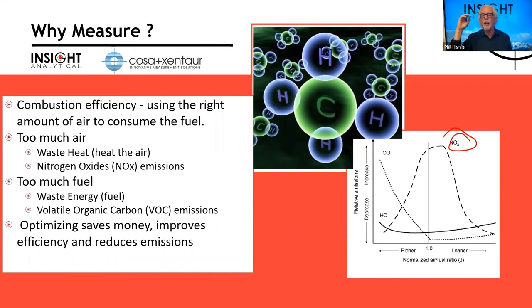But when we're trying to optimize an actual operating steam generator or a gas turbine, we want really fast response. We don't want to measure after the fact. Ideally, we want to measure before. We want to get a measurement or an idea of what we should set the air level at and do what we like to call feed forward control. It gives us faster response.